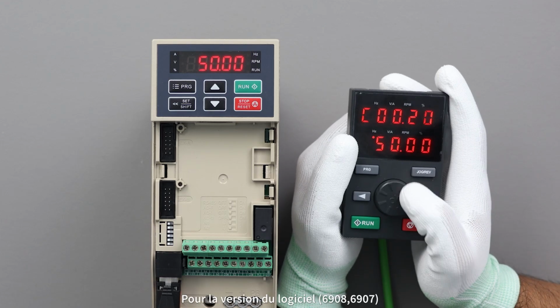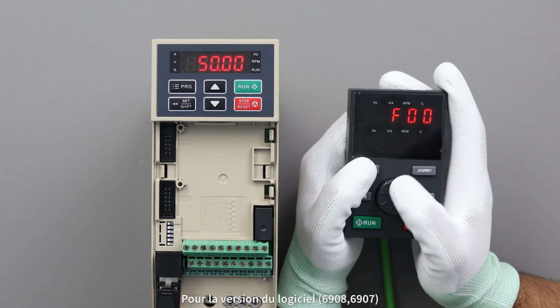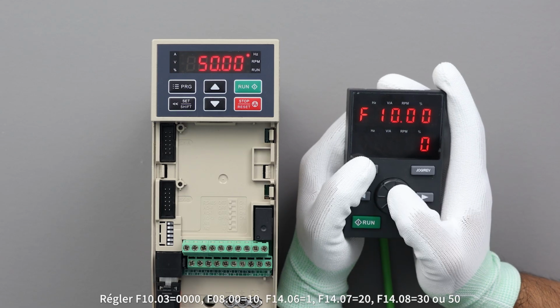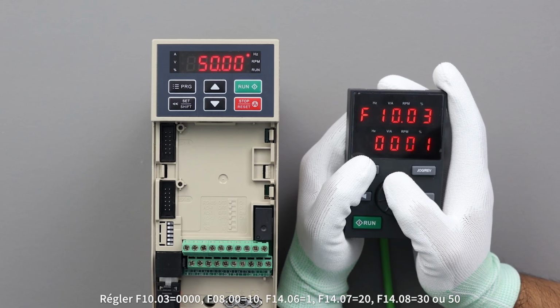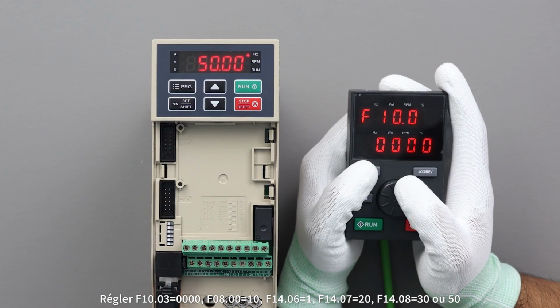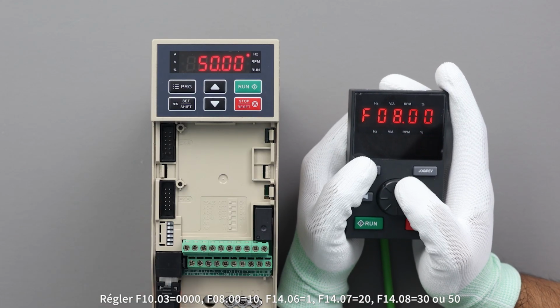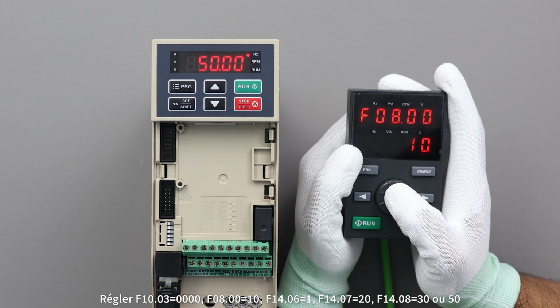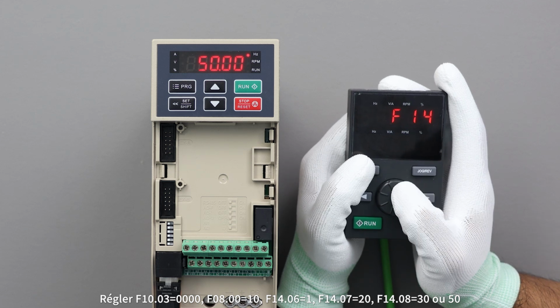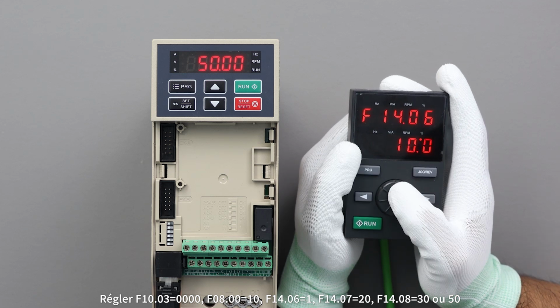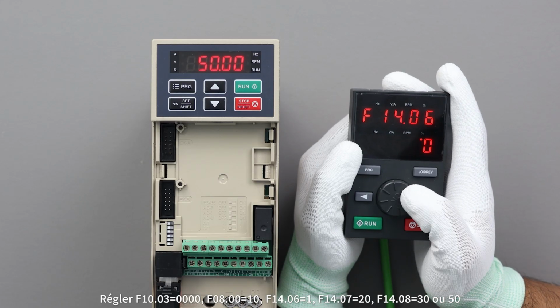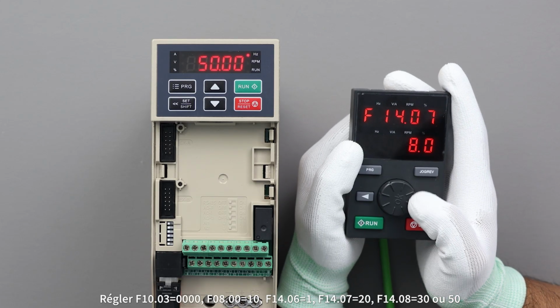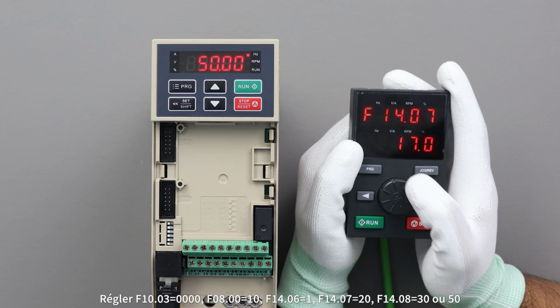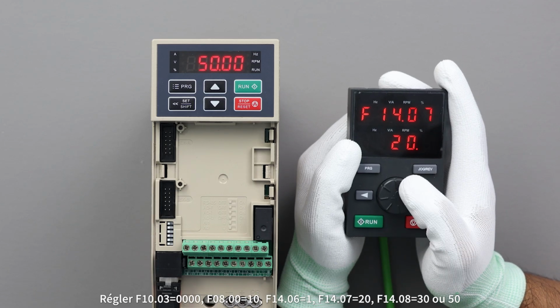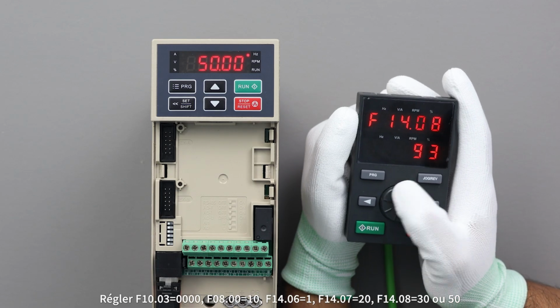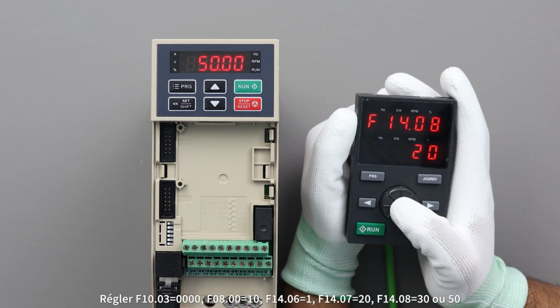For software version 6908 and 6907, set F10.03 to 000, F08.00 to 10, F14.06 to 1, F14.07 to 20, F14.08 to 30 or 50.